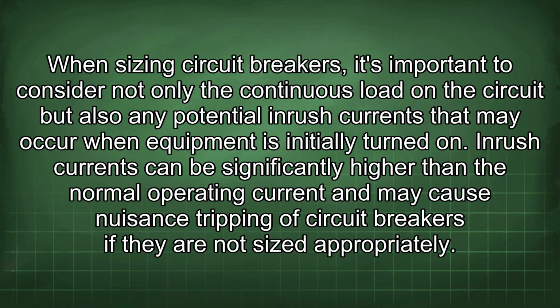When sizing circuit breakers, it's important to consider not only the continuous load on the circuit but also any potential inrush currents that may occur when equipment is initially turned on. Inrush currents can be significantly higher than the normal operating current and may cause nuisance tripping of circuit breakers if they are not sized appropriately.